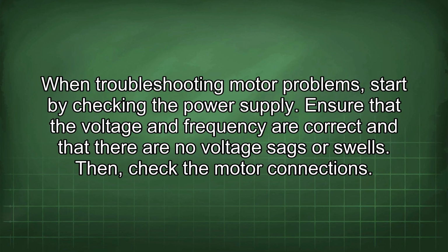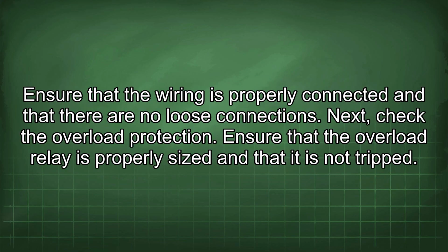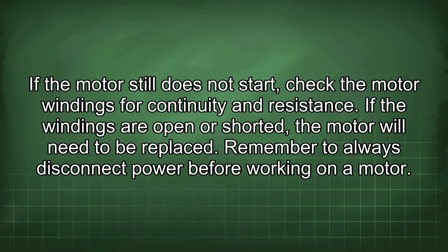When troubleshooting motor problems, start by checking the power supply. Ensure that the voltage and frequency are correct and that there are no voltage sags or swells. Then check the motor connections. Ensure that the wiring is properly connected and that there are no loose connections. Next, check the overload protection. Ensure that the overload relay is properly sized and that it is not tripped. If the motor still does not start, check the motor windings for continuity and resistance. If the windings are open or shorted, the motor will need to be replaced.